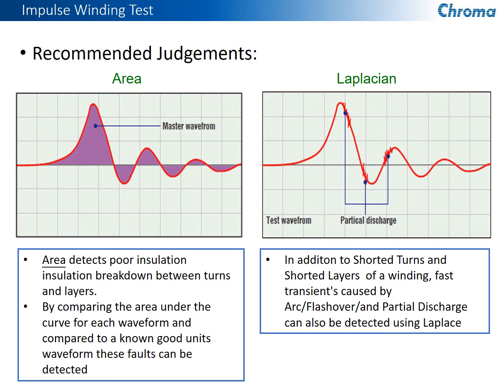When we do the Laplace test, what we're looking for is a very fast transient change in the waveform that would be caused by something like an arc or flashover or partial discharge. But of course, it can also detect a complete breakdown in the winding itself between layers or between turns. So this is another great test that we perform to give you that added insurance that the unit you're testing is going to be good, it's going to pass, and it will work well when it gets to the field.